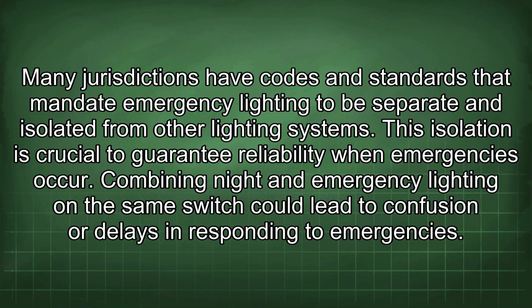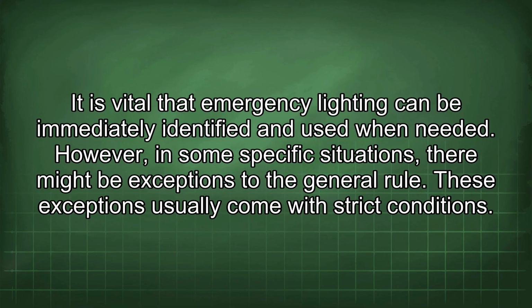Combining night and emergency lighting on the same switch could lead to confusion or delays in responding to emergencies. It is vital that emergency lighting can be immediately identified and used when needed. However, in some specific situations, there might be exceptions to the general rule. These exceptions usually come with strict conditions.